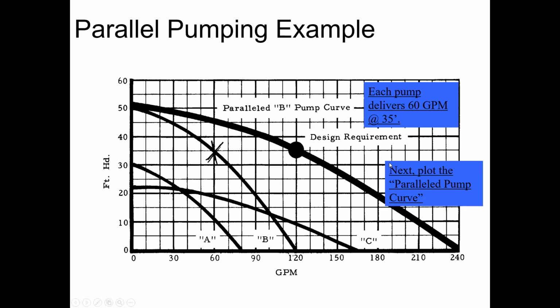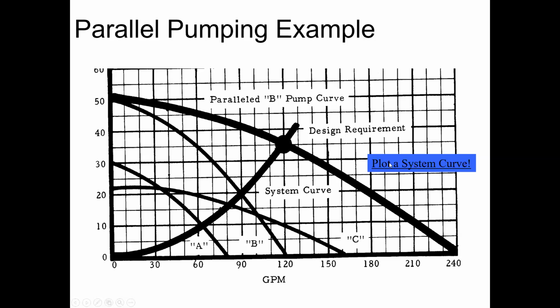And all the way along, and again, software does it for us automatically, but here's my design conditions and here's the operating point when both pumps are running. And then the last part of that equation would be, okay, great, I've met my conditions. One pump is running. What happens? So to know that, I build that system curve. And again, that's going to happen on your computers, on your software. But for you, you just want to know when I'm looking at that, what is that line? Oh, that's a system curve. What's it based on? 120 at 35.